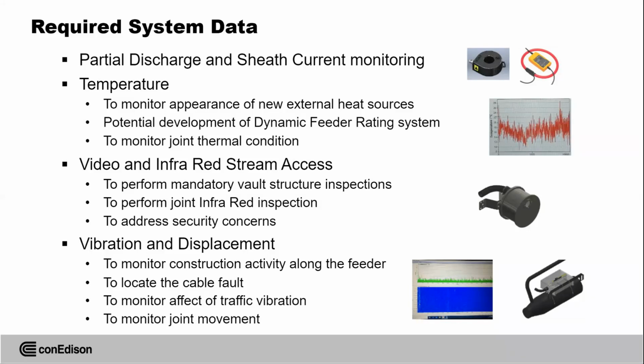It also can help us locate a cable fault, because when we put each individual phase in a different duct, when a failure happens, especially a single phase to ground failure, there is going to be a huge electromotive force, and that cable will jump in the pipe and create significant sound and strain, and the fiber can detect it. Basically, right after the failure, within the next few minutes, you already know where the failure is, how many feet from each manhole. It can also monitor the effect of traffic vibration. And we will also install displacement sensors to monitor joint movement.